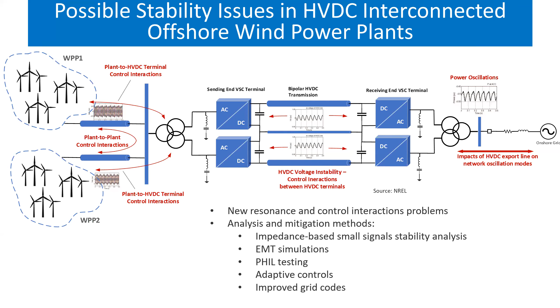Impedance-based stability analysis is a newer tool, and NREL is doing a lot of research in this area. My colleague Shahil Shah is a world-known expert here. The main advantage of impedance-based analysis tools is that it avoids intellectual property limitations, because valid analysis normally requires a very detailed proprietary model of these power converters, which is not easy to get from vendors. With small-signal, impedance-based analysis, you can identify all potential resonances and instabilities at different interfaces in offshore wind power plants at the analysis stage, and either address them in the design or develop controls to mitigate them during operation.